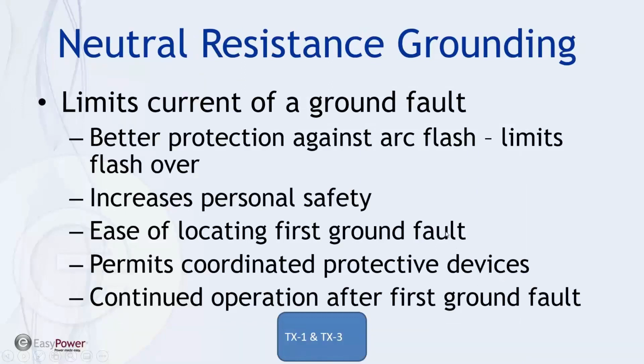Okay, let's talk about neutral resistance grounding. A lot of designs, especially more so recently, are including high resistance grounding of the neutral leg. This is to limit the ground fault, which has several benefits, including increased personal safety, because you're going to fault on the first basic ground fault that you have. It makes it easy to locate it. The disadvantage of a hard ground is that it can tolerate very high current before the system really will shut down.